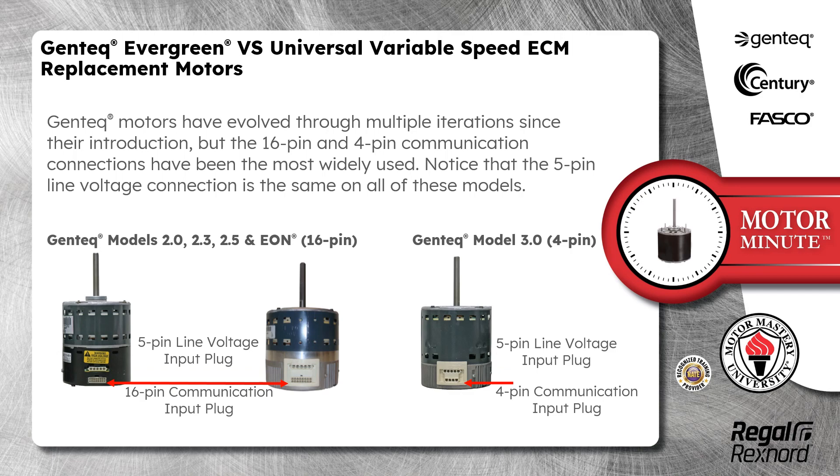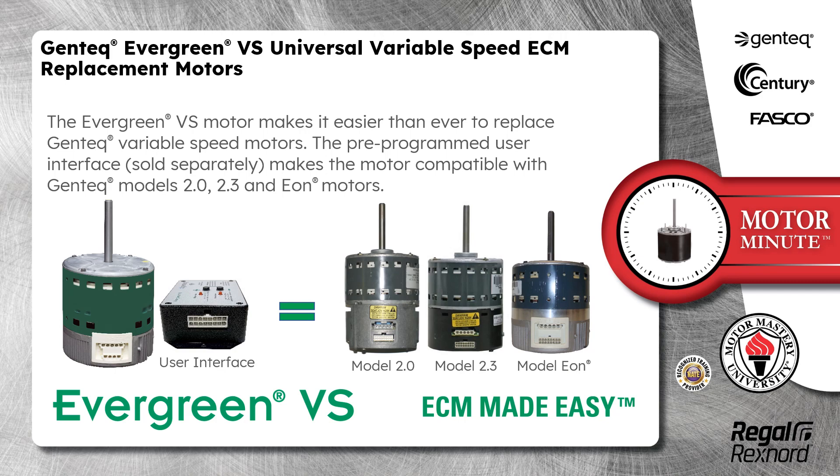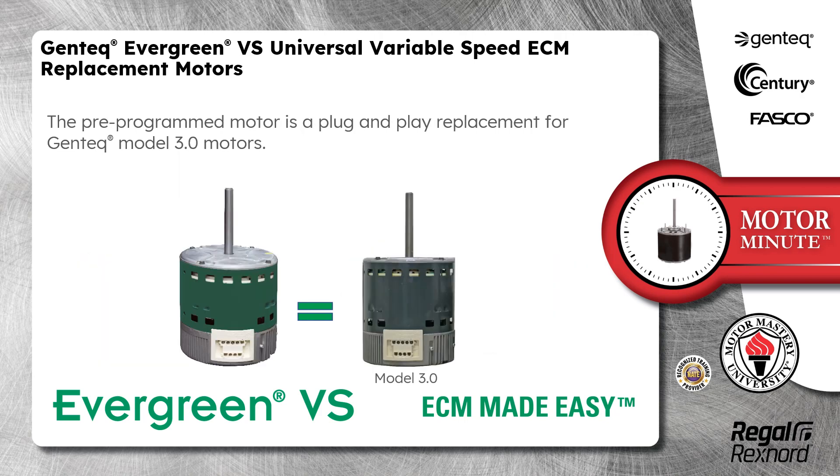Notice that the 5-pin line voltage connection is the same on all of these models. The Evergreen VS Motor makes it easier than ever to replace Genteq Variable Speed Motors. The pre-programmed user interface, sold separately, makes the motor compatible with Genteq Models 2.0, 2.3, and EON Motors. The pre-programmed motor is a plug-and-play replacement for Genteq Model 3.0 Motors.